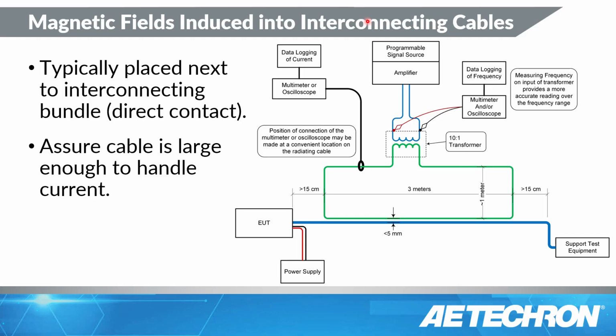These test levels are a little confusing to understand. You're going to see them in the form of, say, 30 amp meters. What that means is the total current times the length of wire that's exposed. 3 meters are exposed here. That means you need 10 amps of current in that wire times the 3 meters, and now you have 30 amp meters.